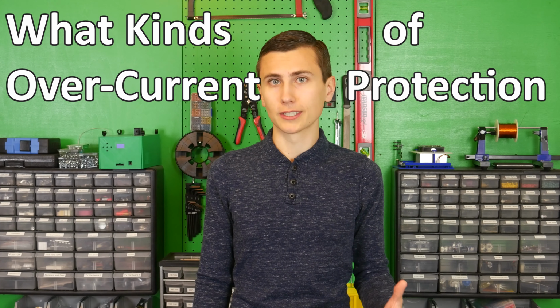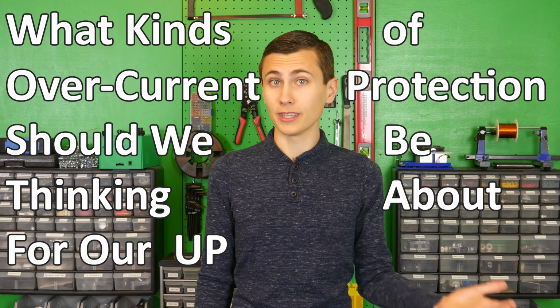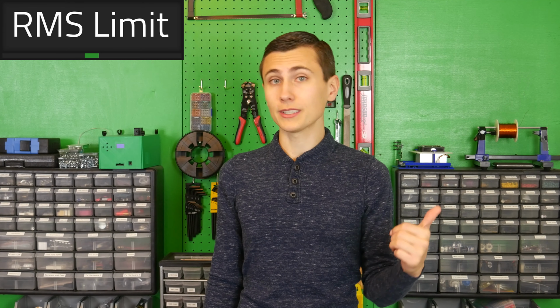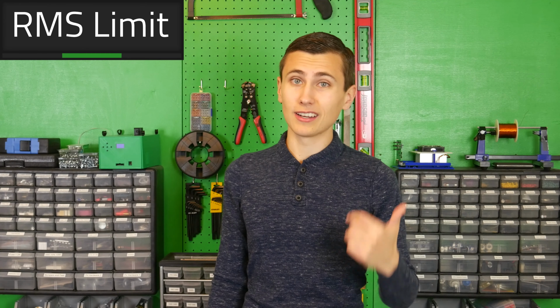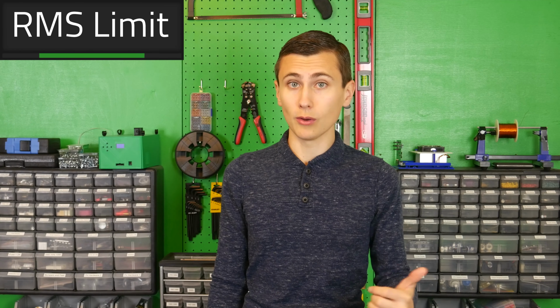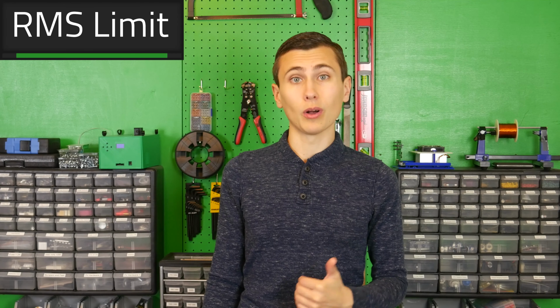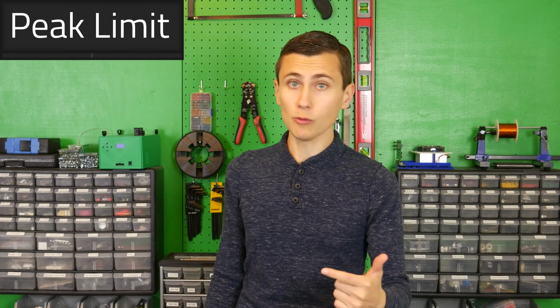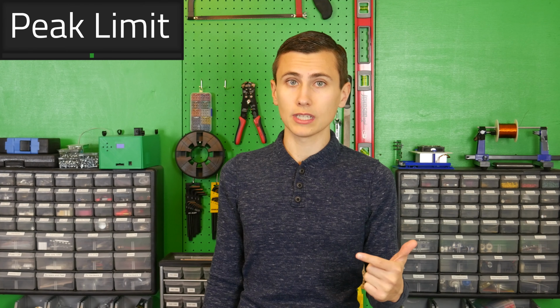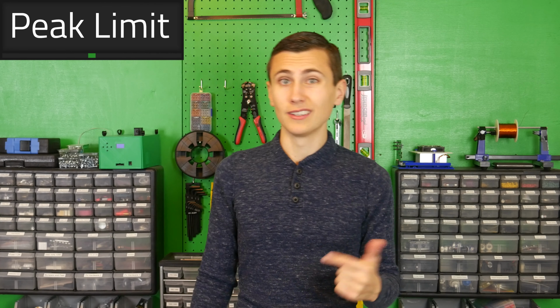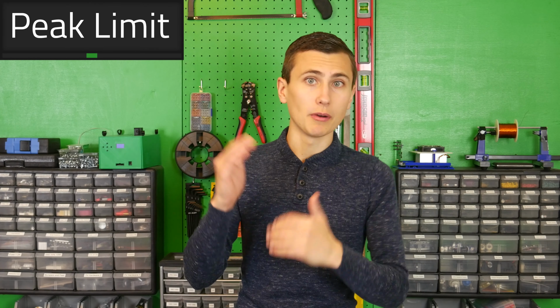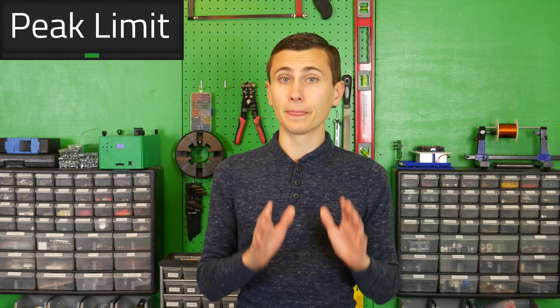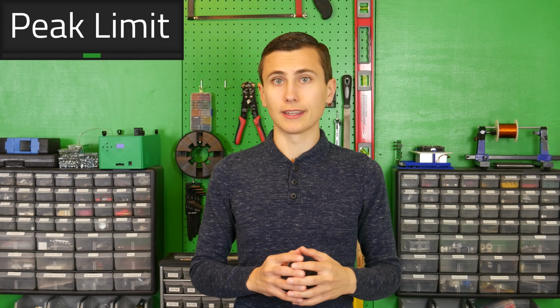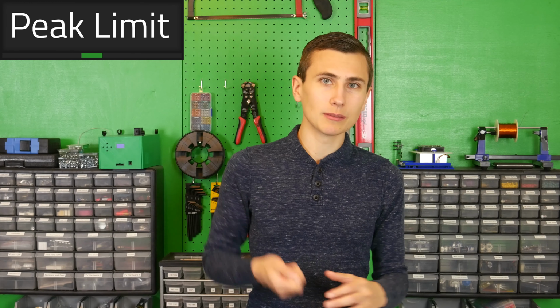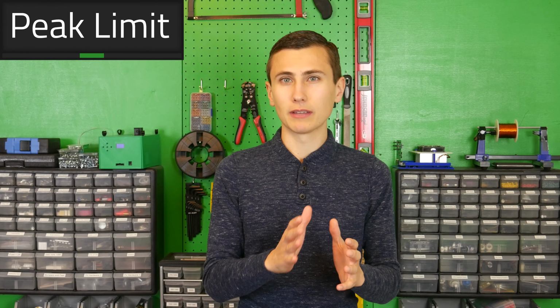That's a pretty good transition into our first topic. What kinds of overcurrent protection should we be thinking about for our UPS? 3 limits immediately come to mind. I think that we should be limiting the RMS output current. This one's pretty basic, and it prevents the UPS from becoming thermally overloaded. It's a very important limit. While we're at it, I think we should also limit the peak output current. And this will trigger the soft start routine if too much current is demanded by a downstream load, so we should probably set that pretty high above our regular operating current limit. This is mainly for short circuit protection on the output, and there might be some inrush currents that could trip it. We'll have to be careful.